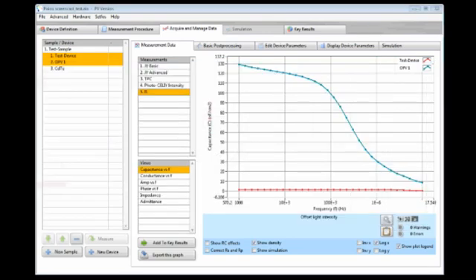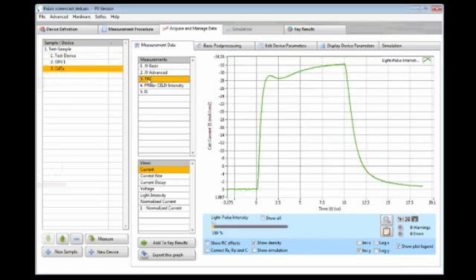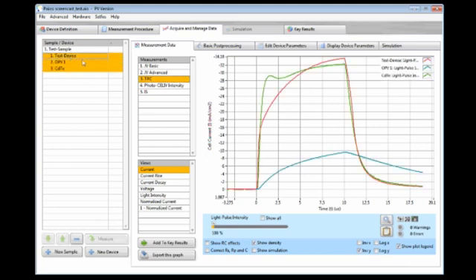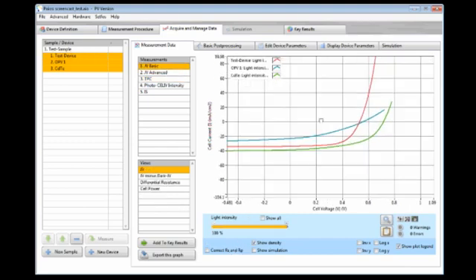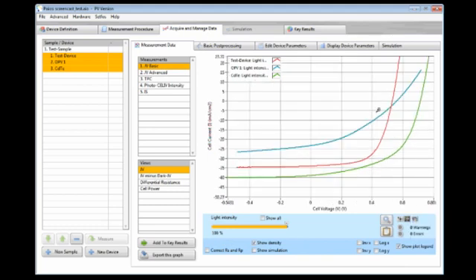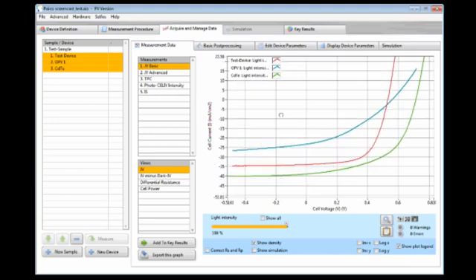The measurement has finished so let's now have a look at the results. So here is the cadmium telluride cell. And when I go to transient photocurrent, here you see that the current rise looks completely different compared to the two other devices. So I can now select all devices together and we see that this rise here in current when we flash a cell with light is completely different. What means that the charge carrier dynamics here are really different. And these charge carrier dynamics we only see in transient measurements. When we compare the IV curve like here, we cannot distinguish here the charge carrier dynamics. We see that the IV curves are different but to learn more about charge carrier dynamics like mobilities, charge trapping and so on, we need to go in the transient domain.